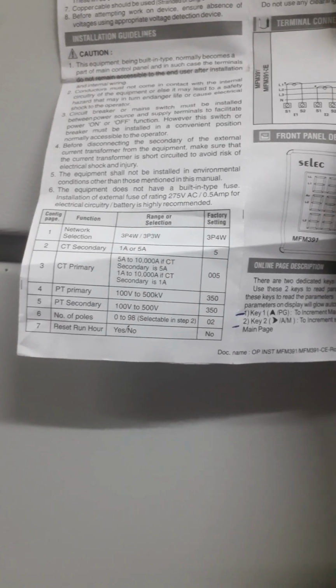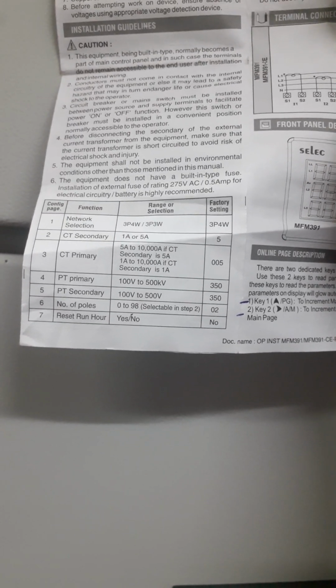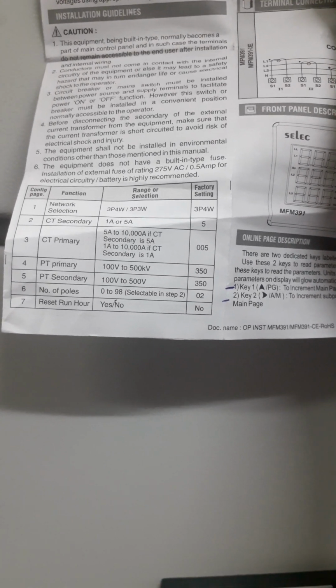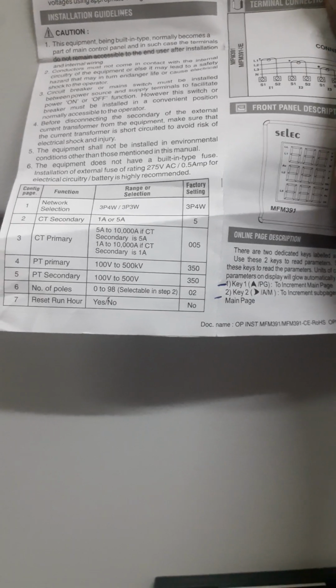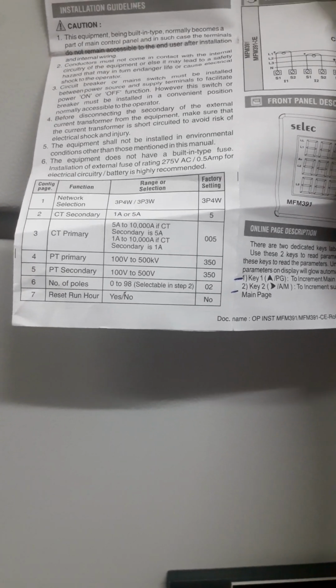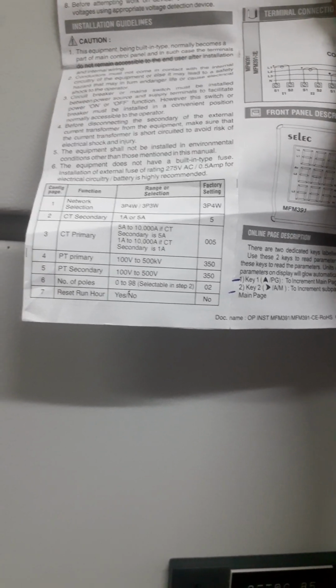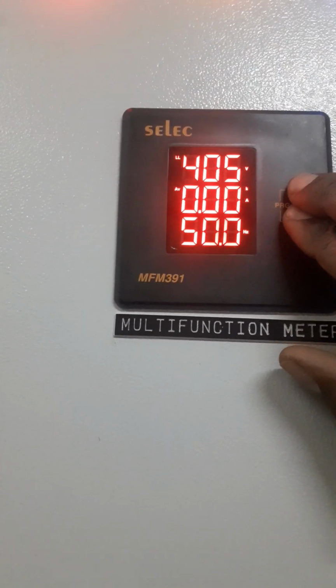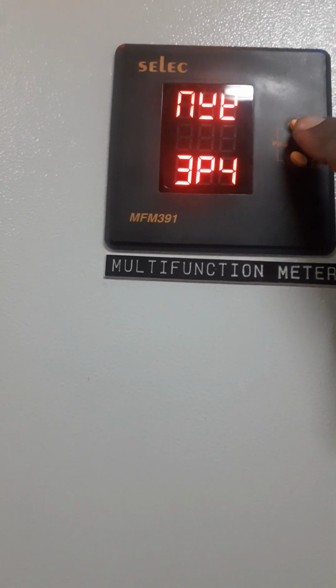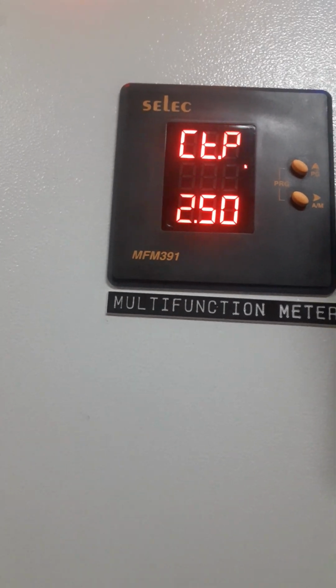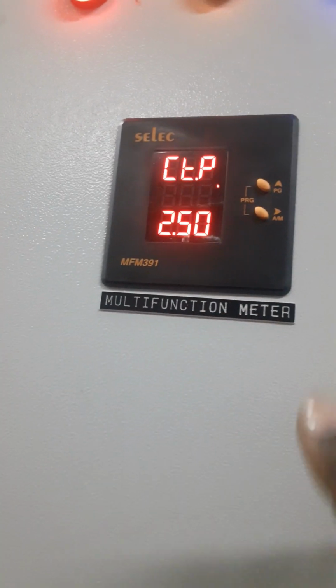Then we shall set our CT secondary, our CT primary, and our potential, which in our case we shall set around 400 volts or 380. Then the secondary, number of poles, and the reset run. Now how do you go about it to the next? It has exited already, so you have to press again for 3 seconds so that we can access there. That's our CT. Already I have set it at 2.5K. Initially it was not like that. I'll show you how I went about it.